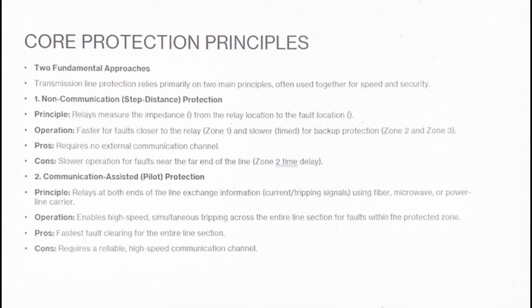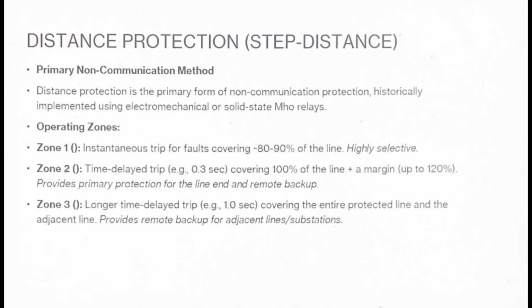The second is communication-assisted pilot protection. This is the cooperative approach. Relays at both ends of the line talk to each other, typically using fiber optic cables. By knowing what is happening at the other end instantaneously, the relays can make an immediate, definitive decision. Is the fault on our line or somewhere else? This allows for high-speed simultaneous tripping across the entire line length, solving the time delay problem of the distance relay.